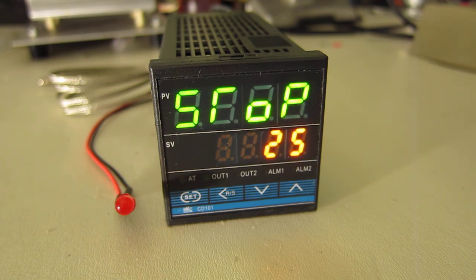In this particular case because stop is not functional you actually have to remove power from the PID controller in order to disable the outputs.